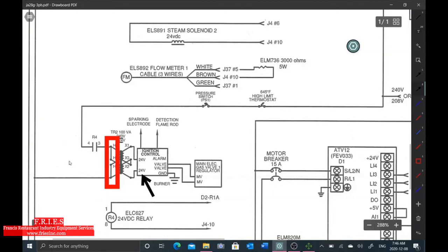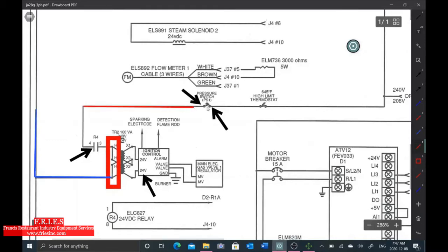Okay, so the next point here is this relay. This relay is really hard to access, so I'm not going to test this relay. I'm just going to go to the next thing in line, which is this pressure switch. I'm going to test the outlet and the inlet of the pressure switch, and I'm going to test it to my L2 right here. Blue to red. I don't want to test red to red, because this line here is red. It's very important that you know which line you're testing to. You don't want to test L1 to here, because then you're going to get potential difference. So I'm going to test here. If I get 0 volts, I'm going to test here. If I get 0 volts, I'm going to keep working backwards.